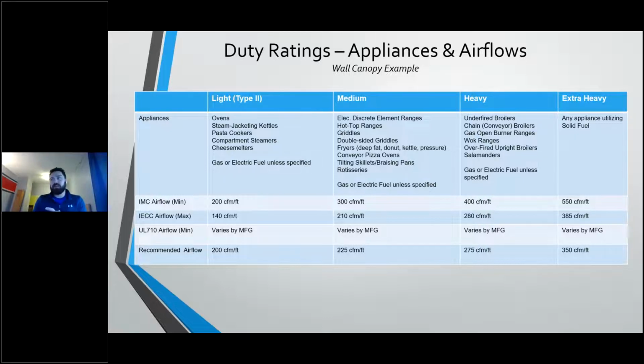Now, I'm not going to talk too much about solid fuel in this presentation. If there's follow-up, I can certainly have those conversations, but it's just important to note, if you have a solid fuel appliance, that appliance needs to be on its own exhaust hood system with its own exhaust hood, its own exhaust duct, and its own UL 762 exhaust fan. So extra heavy has to be on its own application or its own system.